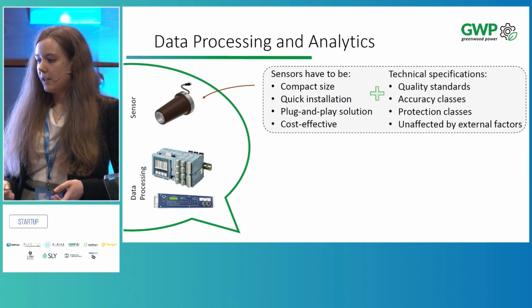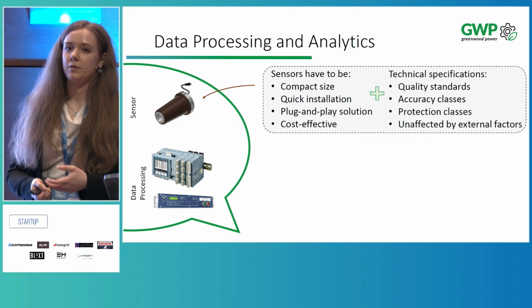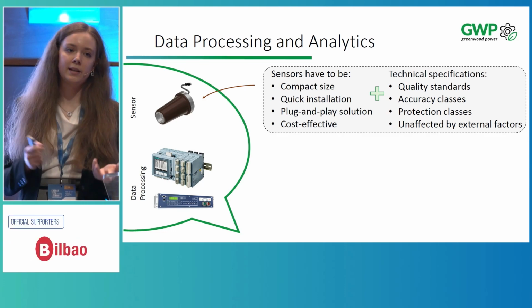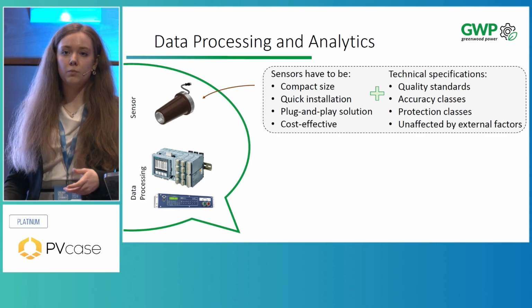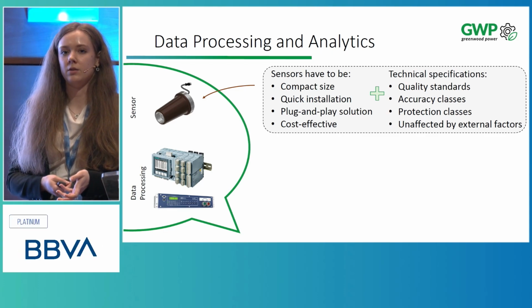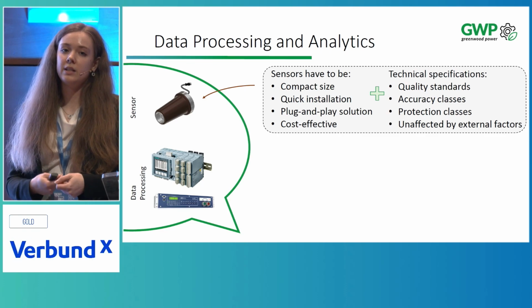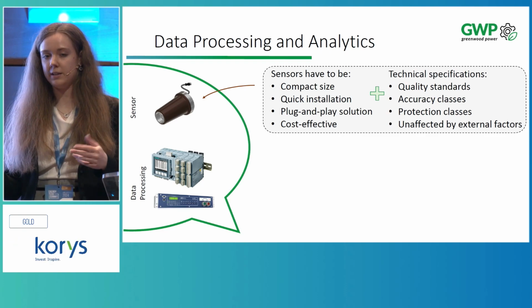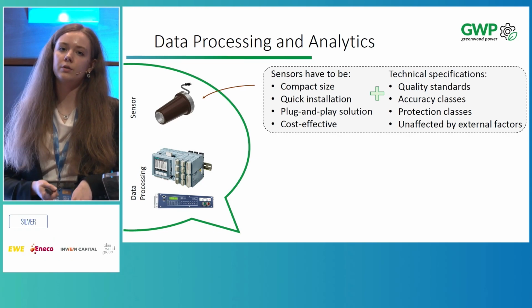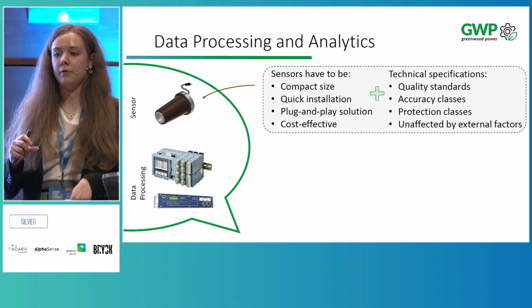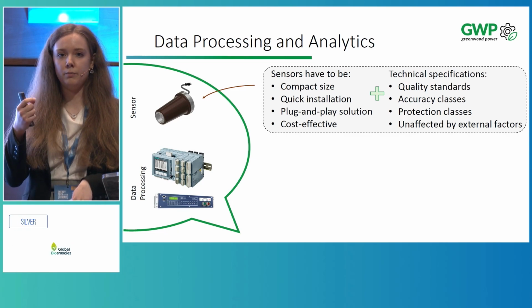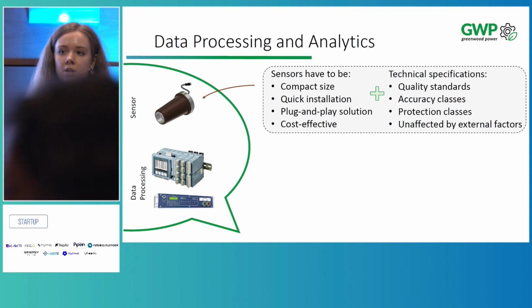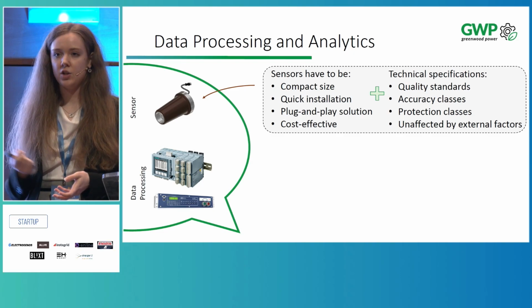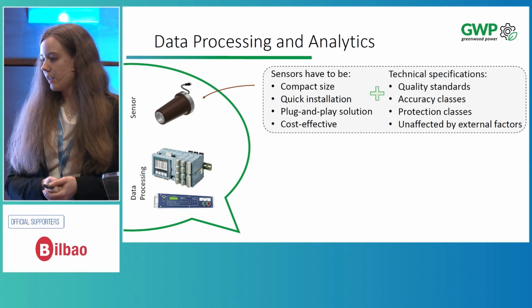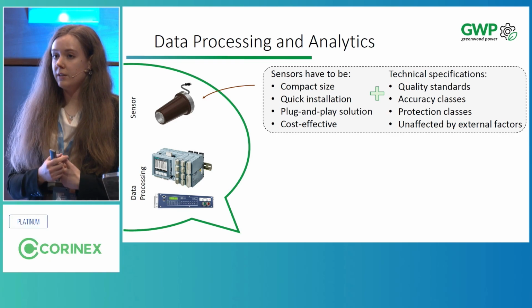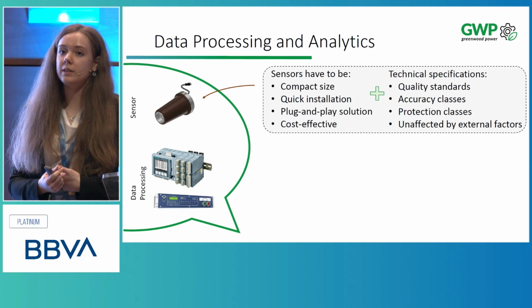There's also the issue of external influences. We all know there's an electrical field and a magnetic field, and both influence the sensor. So the sensor has to resist neighboring fields, since in three-phase systems the phases are very close together. If a sensor on phase A and another on phase B interfere with each other, we measure inaccurate data.